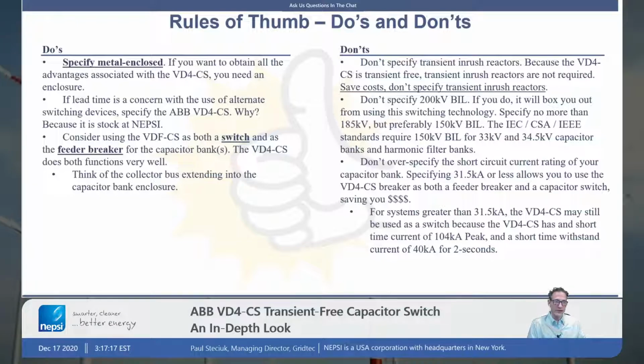Will 31.5 kA be sufficient? And oftentimes the answer is yes. So if you specify 31.5 kA, we can use the VD4-CS as both a breaker and a switch. So it gives you some cost savings because, again, we can eliminate that upstream feeder breaker. And don't forget, if the fault current is above 31.5 kA, you can still use the VD4-CS. Why? Because there's a 104 kA peak withstand current and also a 40 kA 2-second rating on that switch. So it can still be used for the purpose of switching. We just can't use it for interruption.